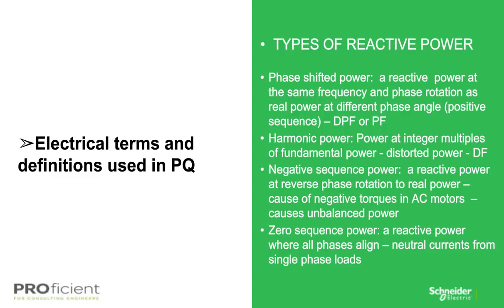And then lastly is zero sequence power, which is a result of single-phase loads attached to neutrals. It typically refers to harmonics on the neutral conductor. They're also called triplen harmonics. And again, we'll get a little bit more into that later with some applications, because the harmonics that are multiples of 3 add directly on the neutral, massively amplifying the harmonic currents on the neutral conductors.